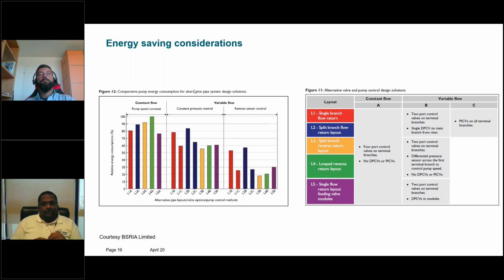So what would be the location of the intelligent valve on a district cooling plant? Is it going to be in the energy transfer station or is it going to be somewhere else? That depends on the energy transfer station in the district cooling network. If you have an energy transfer station which is decoupling with a heat exchanger from the district cooling system into the building system, and if you have a temperature level change from the district cooling network to the building system, then you can install an intelligent valve in this transfer station and use the delta T control to avoid too low delta T's.